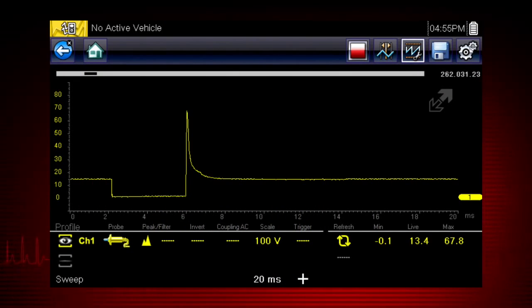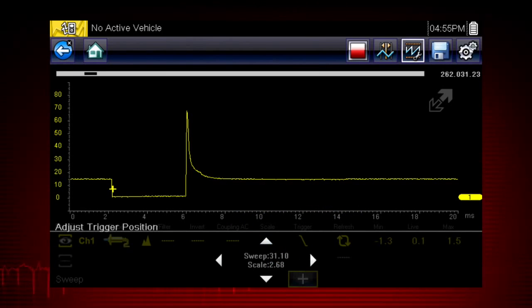The scope trigger sets a threshold value that initiates the waveform display. When the voltage passes the threshold value, a new waveform begins. This produces a very stable waveform that does not flicker or drift. Touch the trigger icon to trigger when the voltage rises to the threshold value. Touch the icon again to trigger when the voltage falls to the threshold value. The trigger point appears as a plus sign on the display. Touch and drag the plus sign to position it, or touch the large plus sign on the control panel to use the four-way control for a more precise setting.